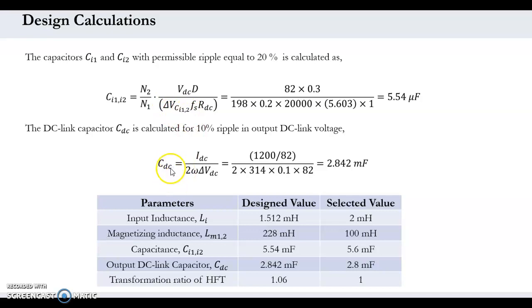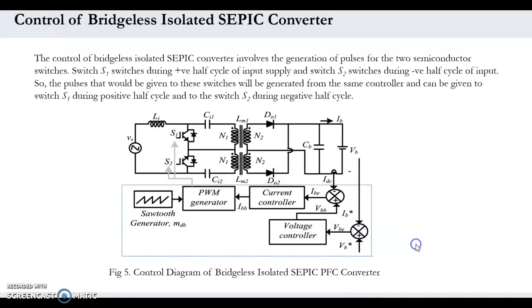Then the DC link capacitor value is also calculated. The designed values are: input inductance Li equal to 2 millihenry, magnetizing inductance equal to 100 millihenry, capacitance values Ci1, Ci2 equal to 5.6 microfarad, output DC link capacitor CDC equal to 2.8 millifarad, and the transformation ratio of the transformer is taken as 1.